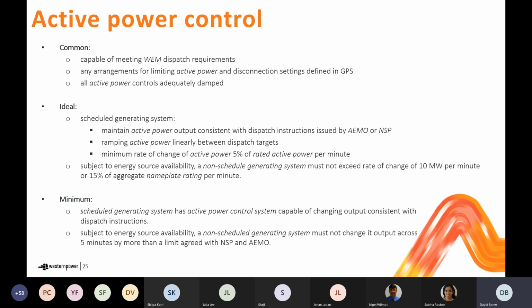And a common requirement that appears for many of these technical requirements is for the controls to provide adequate damping. You'll see when we step through this one, we introduce the phrase subject to energy source availability. This has been introduced a lot across many of the technical requirements, and it's a way of making the requirements able to be applied to both traditional synchronous generators and to renewable generating systems. So what it means is a renewable generating system is probably not able to control the amount of energy that's available to it at any given point in time. For instance, it's normally the case that your solar farms will seek to be operating to produce an amount of power compatible with the amount of daylight falling on the solar farm. If that amount of daylight changes, then so does the output of the solar farm.